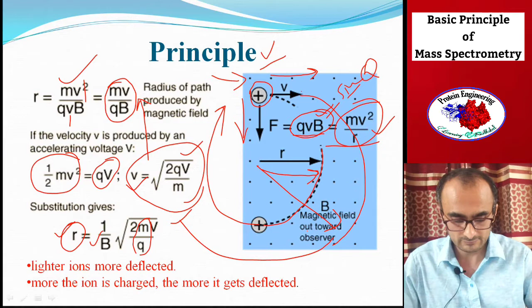In a mass spectrometer, there are four fundamental units. The first is ionization. You have an ionization chamber where a sample is introduced, and the sample has to be in a gaseous, vaporized state. Initially it could be solid, liquid or whatever, but when it enters the ionization chamber, it should be in vapor state. In the ionization chamber, the analyte is ionized; there are many methods available for ionizing different types of samples, and one of them is used here to give charge to the analyte.